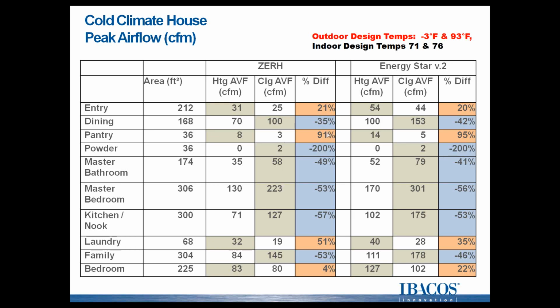So there's a lot of numbers on this chart, but I'd just like to point out that the difference between heating airflow and cooling airflow can be pretty significant. Sometimes it's half the value of one or the other. And so as a designer, people are often faced with the question, which airflow do you deliver? If you deliver, say, the greater amount of airflow during one season, you might under-condition or over-condition that space during the other season. So there's a challenge here that doesn't have a direct answer. But we'll try to discuss some of the ways around that.